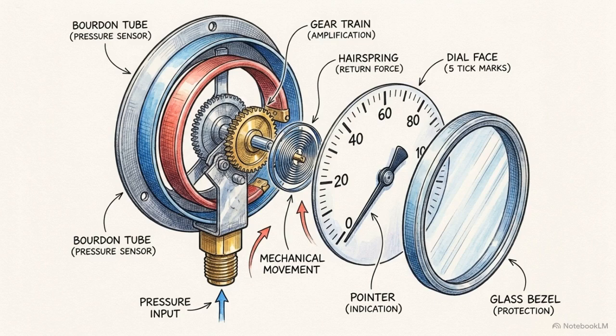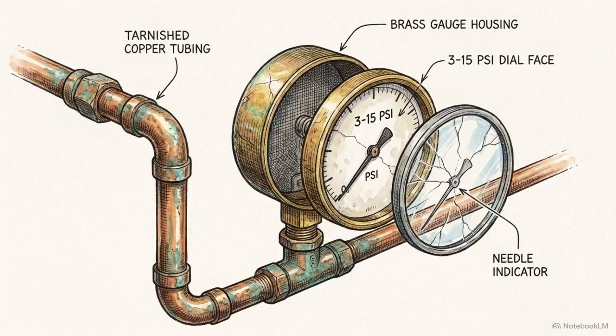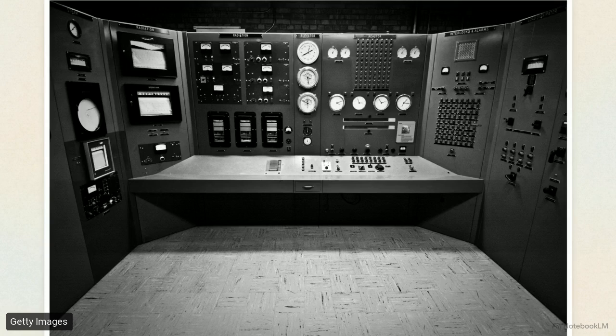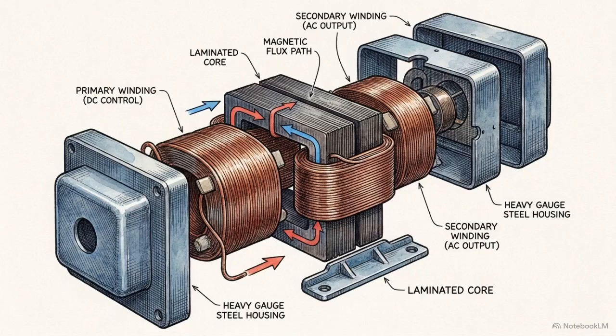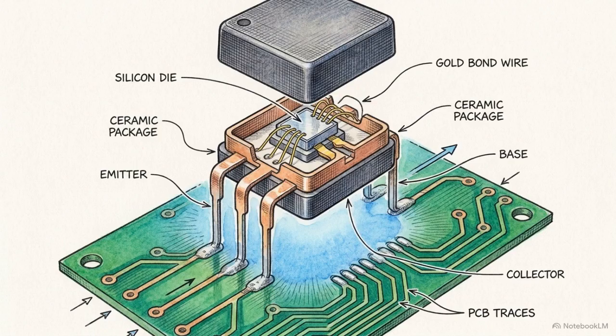The specific scale of this loop, 4 to 20, follows a 1 to 5 ratio. That math inherited the legacy of the old 3 to 15 psi pneumatic tubing used in early factories. When those pneumatic tubes were replaced by early electronic control rooms in the 1950s, the first standard was set at 10 to 50 milliamps. The bulky magnetic amplifiers of the era required at least 10 milliamps just to operate. The invention of highly stable silicon transistors allowed engineers to drastically scale down those power requirements, arriving at the 4 to 20 standard we use today.